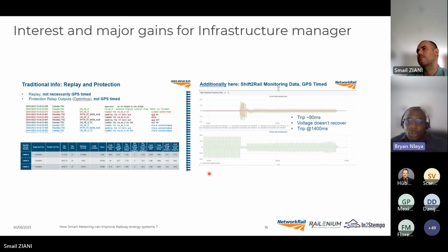In summary, this system is quite helpful—it gives us a lot of visualization and information. We've got other examples, some of which you've seen, in terms of regenerative braking. We can also look at things like THD and harmonics, and record disturbances that haven't necessarily resulted in the protection system operating, like arcing, system disturbances, transient high voltages, or transient overcurrents. This helps us determine the condition of the system.